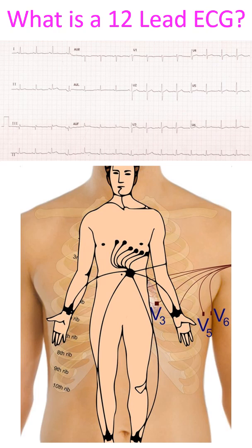Standard 12-lead ECG consists of 6 precordial leads, 3 conventional limb leads and 3 augmented limb leads. Ideally, electrocardiographic data from all 12 leads should be simultaneously acquired. Some electrocardiographs acquire 3 channels simultaneously while others record leads sequentially in a single channel. The advantage of simultaneous multi-channel acquisition is that any beat can be analysed in all the channels, making analysis of complex arrhythmias easier.